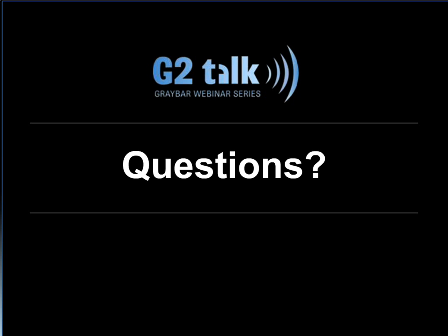Okay. Bonnie is asking, what happens when you have an older LFL ballast with a UL type A? Well, that's one of the catch-22s there. If the ballast fails, you've got a product that doesn't work now. So now you've got a fairly expensive LED tube, which is going to be a lot more expensive than a fluorescent tube. Now you have a choice. You either replace the fluorescent ballast, or you refit it with an entirely different solution. You could take out the ballast and go with a remote driver and a different LED tube that requires a remote driver. That's the risk. Your value proposition starts to fall apart if you buy fairly expensive LED tubes and your fluorescent ballast fails. So the most straightforward thing would be to just replace the fluorescent ballast.